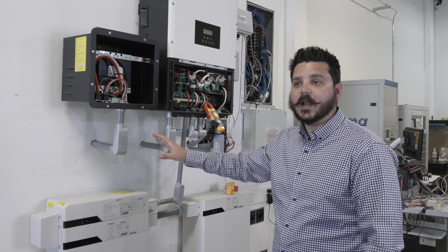A lot of battery backup solutions that are DC coupled have this integrated externally. SolarEdge does this on some of their stuff, and most of these systems where you see a 200 amp auto transfer switch have it integrated into it, like the SMA auto backup unit or Enphase's IQ System Controller 200G.